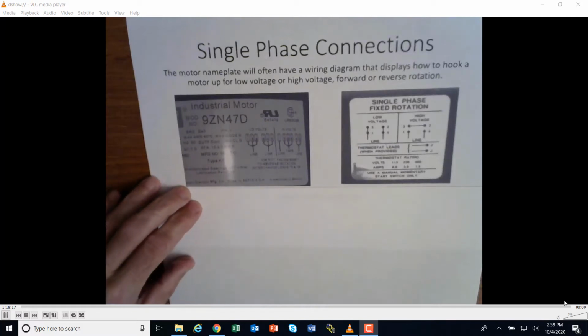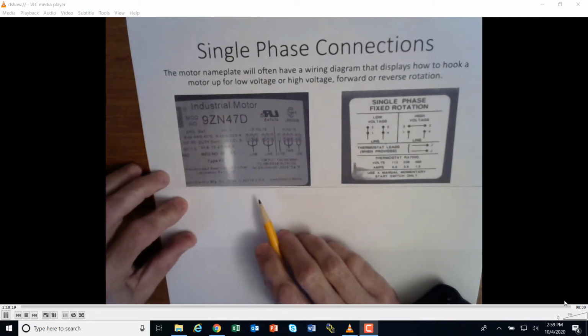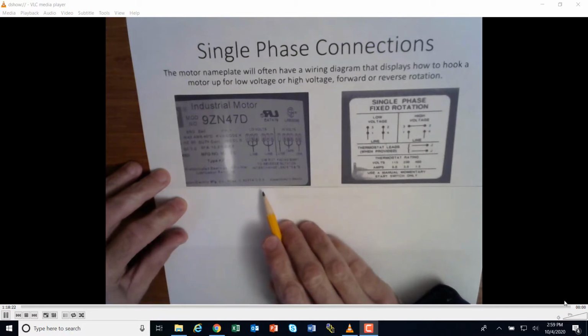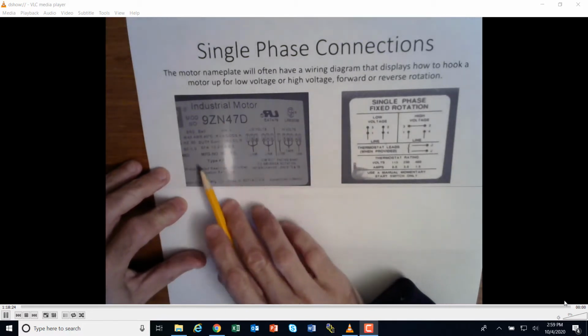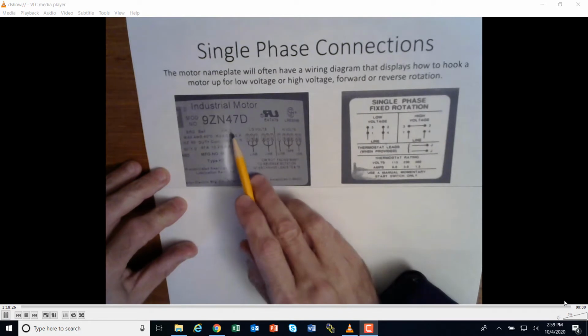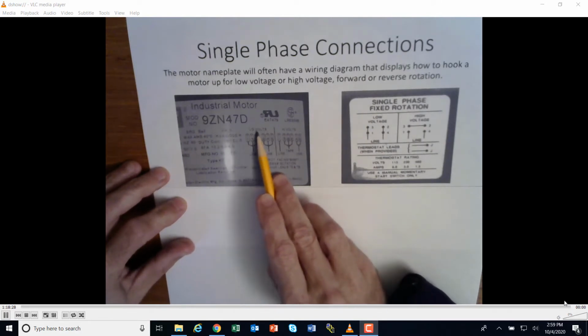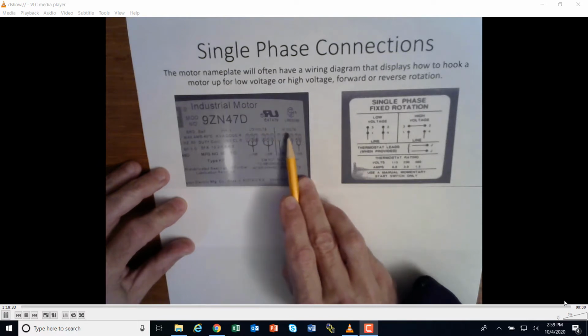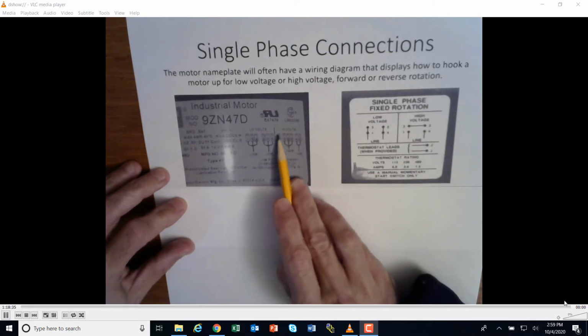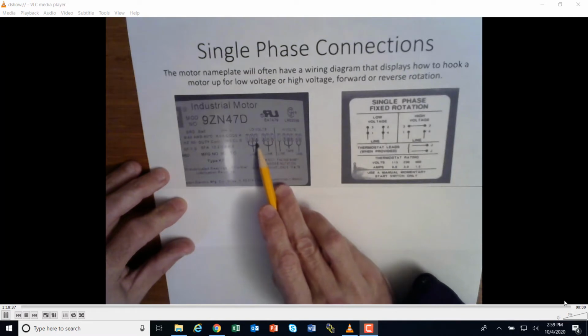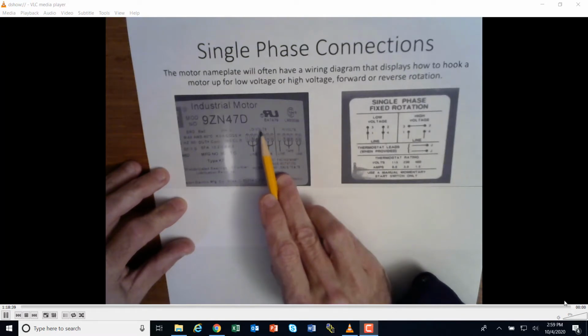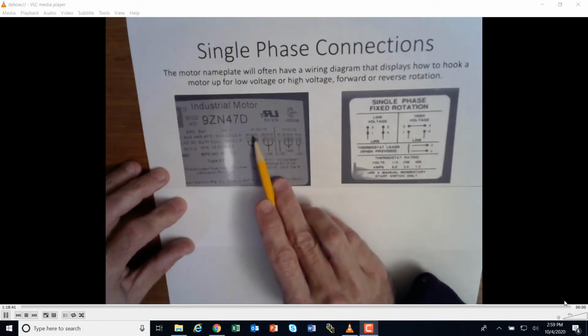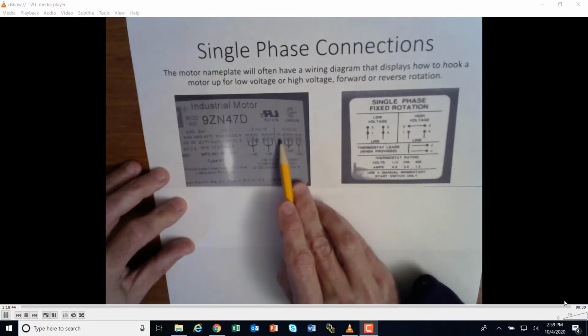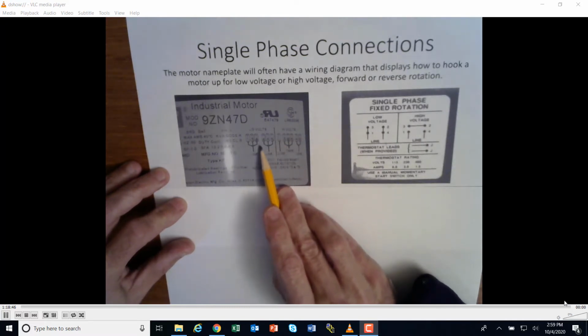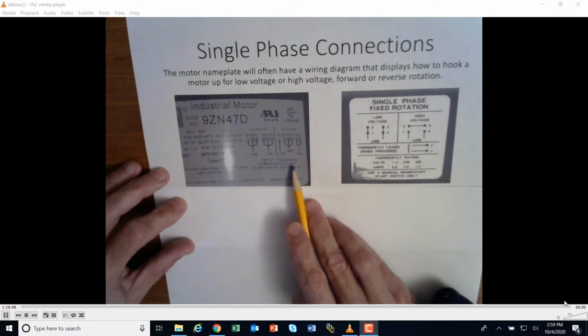Let's take a look at some single-phase motor nameplates to see what kind of information we can get off of them. So take a look at this first one right here. It says it's a single-phase motor right here, and it's saying low voltage and high voltage. So that means we're running at 120 volts or 240 volts or somewhere in that area. There's T1, T2, T3, T4, T5, and T6. So that's a 6-wire motor, and we can wire it differently here if we want to go in low voltage or high voltage, clockwise or counterclockwise.